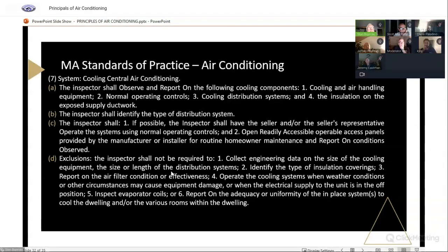That's similar to us, the size or length of distribution systems. The longer a duct, theoretically, as the duct work continues, it should get smaller to maintain pressure, push the air back. I don't see that very often. Maybe the length that I see on a normal basis is enough to stay one size. But the bigger a house, you have to maintain pressure inside the ductwork. So that's where that size and length of distribution systems comes in.